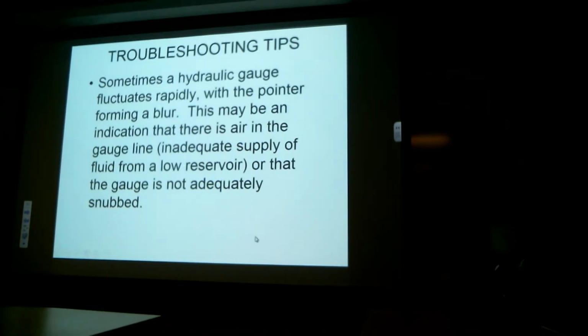Sometimes with a hydraulic gauge, if the gauge fluctuates rapidly and the pointer is forming a blur, that's an indication that there's air in the line. Many times the snubber alone isn't sufficient. Years ago, the mock-up board that we have out in the shop required replacement of the bladder in the accumulator. The problem that I noticed was that the system pressure gauge needle would tend to mysteriously increase in pressure over a period of time, even after you stopped using the hand pump. The problem was the bladder in the accumulator had developed a leak. The nitrogen gas was able to find its way into the fluid. Ultimately, the gas found its way to the bourdon tube of the gauge, and it caused the gauge to indicate an increase in pressure. As that volume of gas reached the bourdon tube, it began to expand, and of course it causes the bourdon tube to straighten, and made the needle sweep upscale. So that was the cause. Again, kind of strange, but that's the way that it worked.